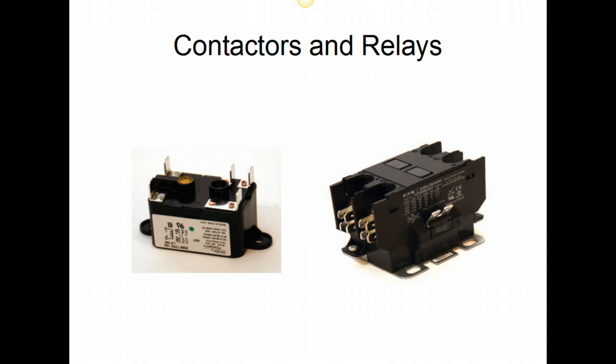Contactors and relays. We're going to talk about these briefly here at the end of this video and get into them a little bit more in depth at the beginning of the next. These are also coil-operated devices. They're a mechanical switch that are operated and activated the same way as the solenoid valves are, except rather than passing a fluid or refrigerant, they will pass electric current and open and close a switch itself.